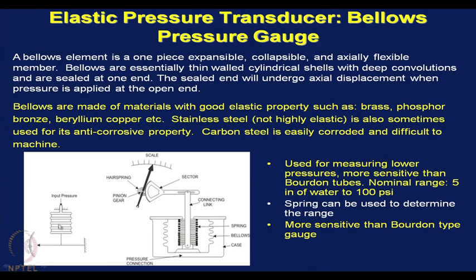This is a better representation of the bellows element. You have the bellows with deep convolutions. It is spring loaded inside, so that the deflection can be controlled, and this deflection is read by this pointer and scale mechanism. So, you have a connecting link and a sector and pinion assembly, which helps this deflection to be read by the movement of the pointer against this scale.